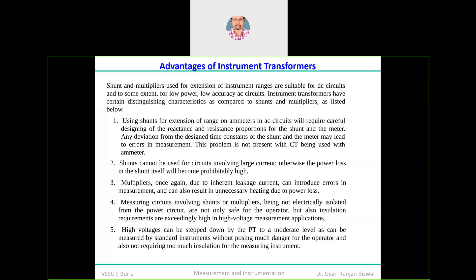Shunts and multipliers can be used for extending the range of an instrument. They are primarily suitable for DC circuits and, to some extent, for low power AC circuits. When you use shunts or multipliers, the accuracy level is very low. When using a shunt device to extend the range of a meter in an AC circuit, you have to take care about the design of reactance and resistance in proportion, because failing to maintain that ratio will give phase error and multiplier error.